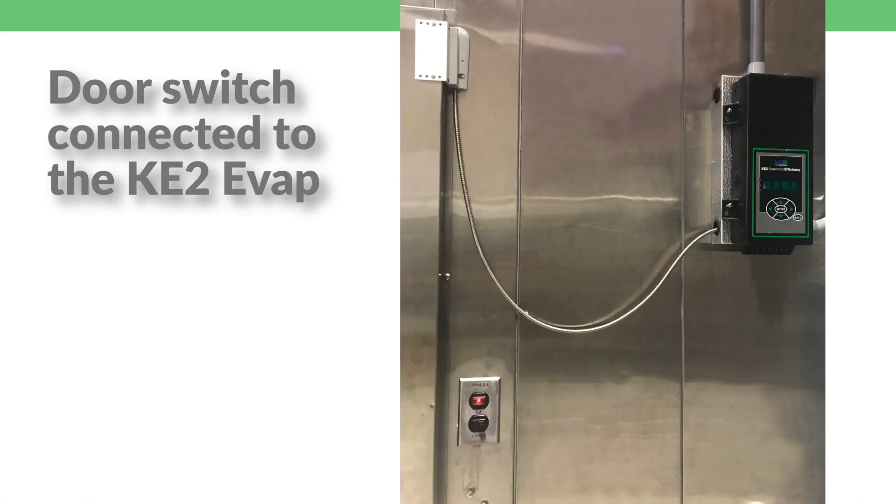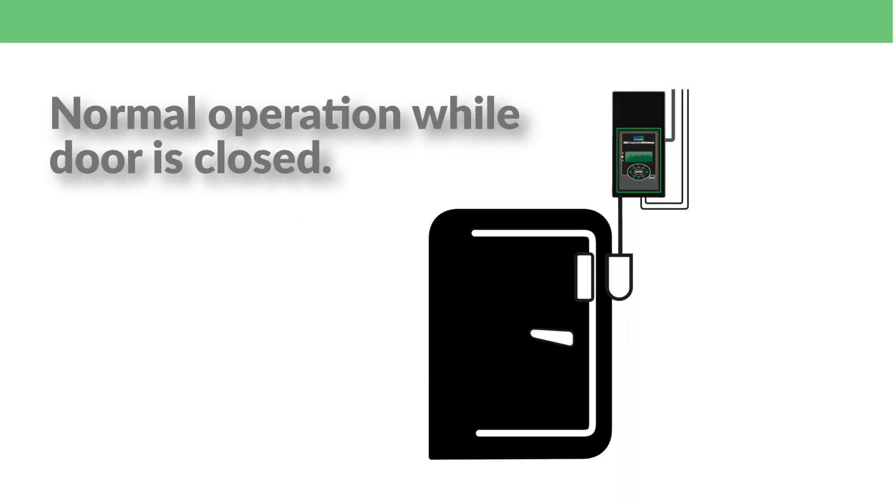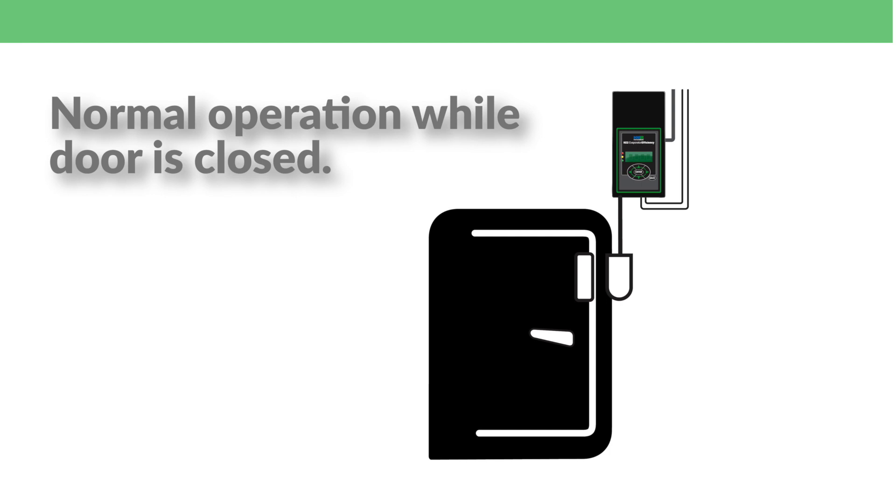With the door switch connected to the KE2 evaporator efficiency controller, for example, the system operates normally while the door is closed. When the door is opened, the evaporator fans are turned off. Once you close the door, normal operation continues.